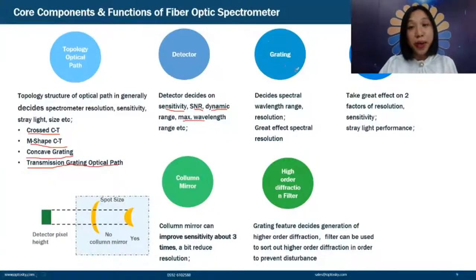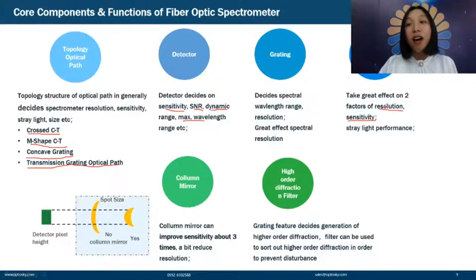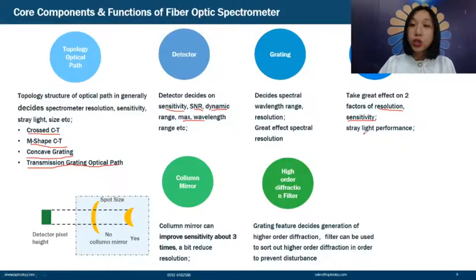Third is the grating, which decides the spectrometer's wavelength range and greatly affects resolution. Fourth is the slit size, which affects both resolution and sensitivity — the smaller the slit, the better the resolution but the weaker the sensitivity. Slit size also affects stray light performance.